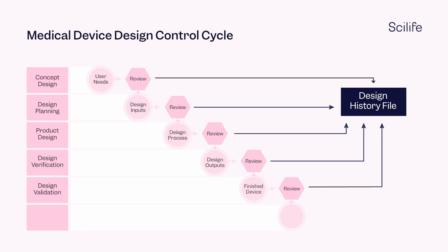The initial batches of the device, or their equivalents, are tested in real or simulated conditions to assess their use and reliability. Other details like risk analysis, software assessments, etc., are also appraised. As with other assessment processes, all details of design validation, device ID, methods, date, person responsible, etc., will be saved in the DHF.